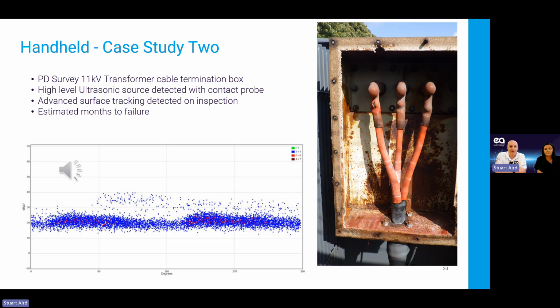So, you know, there are 2 types of ultrasonic sensors. You can have an ultrasonic airborne sensor where you're listening around the gaps. In this case, it's obviously well sealed. It's an outdoor transformer cable termination box, so you haven't got an air pocket to listen to with your ultrasonic microphone. Like the previous case, we actually listened through the vents on the cable box and picked up that sound very easily. In this case, we couldn't do that.